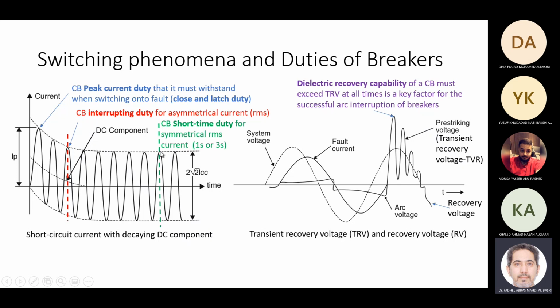In our short circuit calculation, normally what you will get is the steady state current. So when we rate a circuit breaker, when you choose a circuit breaker, at what current should we choose it? Should we choose it to break this current, Shabab, or this current, or this current, or which current do you expect? Shabab? None of them, because it's the normal condition, right? This is the normal current. No, now there's a difference. When I say current rating of a circuit breaker, it is chosen based on the full load current. Now we are talking about its breaking capacity, meaning the ability of the breaker to interrupt short circuit current without being damaged.